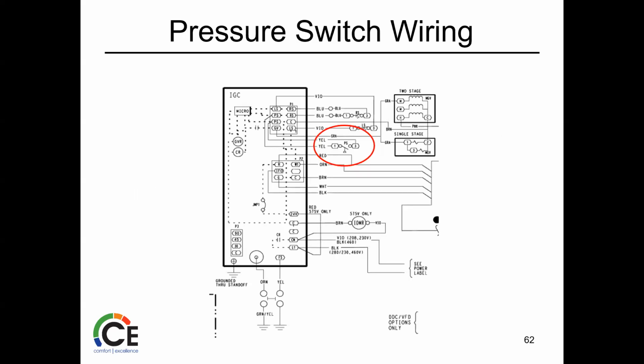There's your pressure switch wiring. It's a basic open close situation. So if it didn't pull closed, obviously it's going to shut you down. Nothing's going to happen. And the board's looking for that 24 volts at that second PS terminal. Let's say, yep, hey, this closed. We're good to go. Now I can start the rest of the sequence.